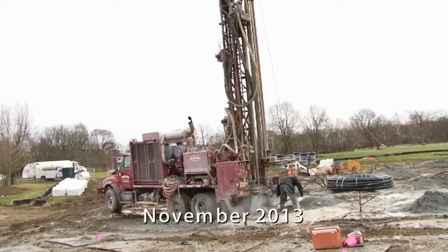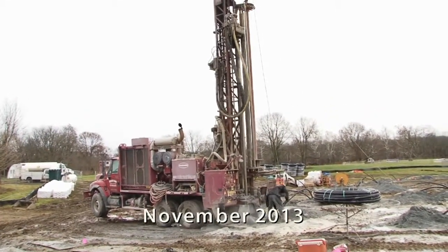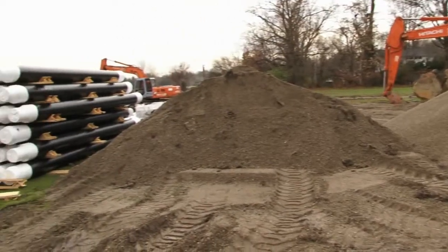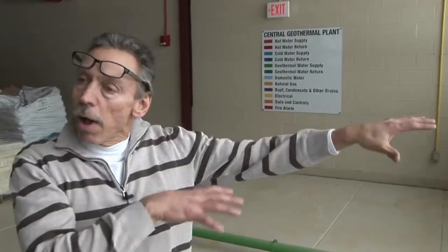Out on South Campus, we had 300 boreholes put in. Those are all tied into a central distribution box. The wells are in circuits of 25. So inside this underground distribution box, if we ever had any problems out in that well field, if we had a leak, for example, we can isolate those 25 boreholes by going down into that vault and turning the valve off, right? And that keeps the rest of the well field working while we're working on that repair. So that's very good redundancy built into that well field.